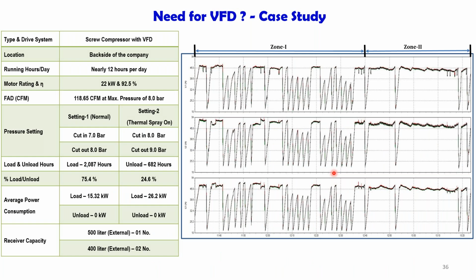This is another case study we conducted on a thermal spraying machine, which is used in manufacturing MPP capacitors for single phase and 3-phase motors. There's an equipment called a thermal spray machine, and that machine consumes a large amount of air from the compressor. So they have a compressor with 2 different settings. When the thermal spray machine is on, the compressor setting is different. When the thermal spray is off, the compressor setting is different. They have a screw compressor with VFD. Somebody told them that VFD will save energy, so they bought the screw compressor with VFD.